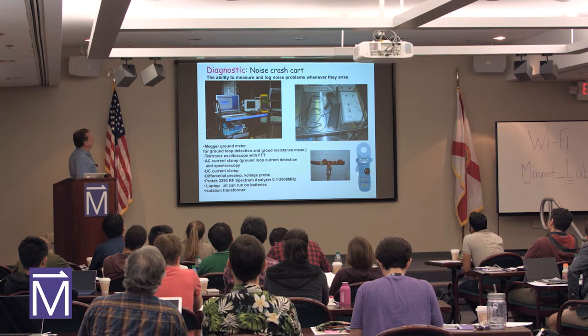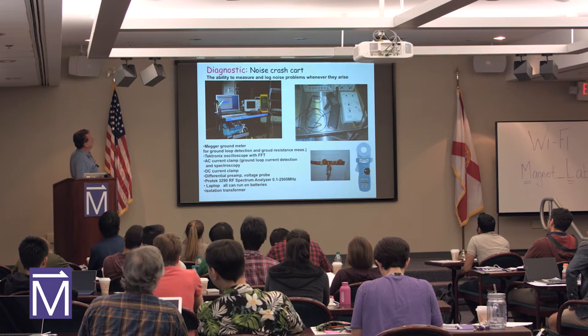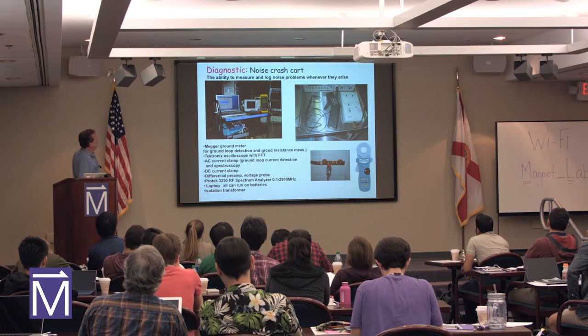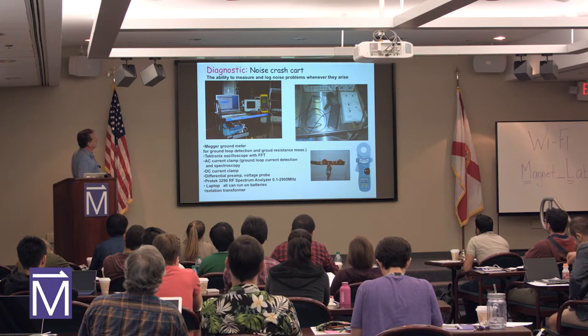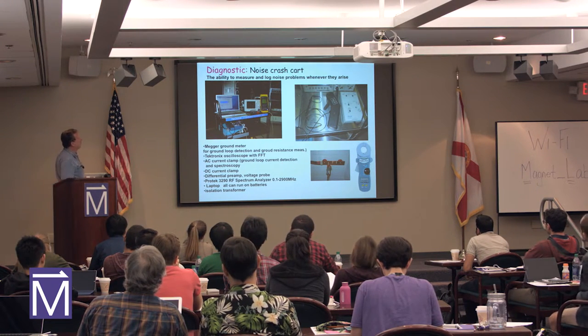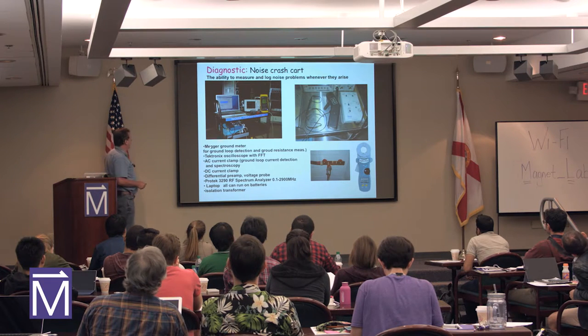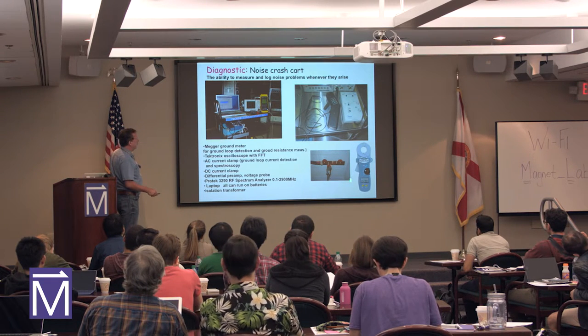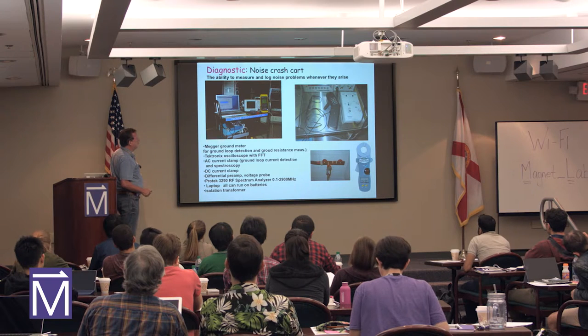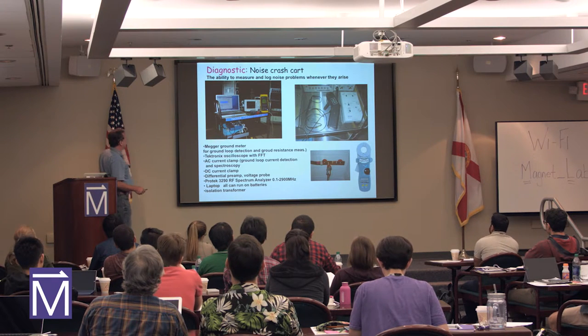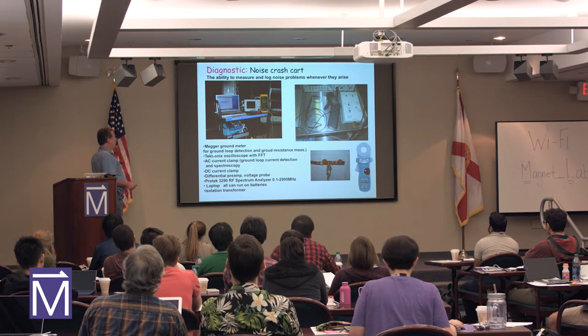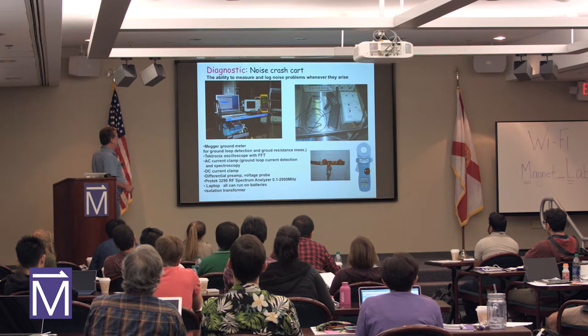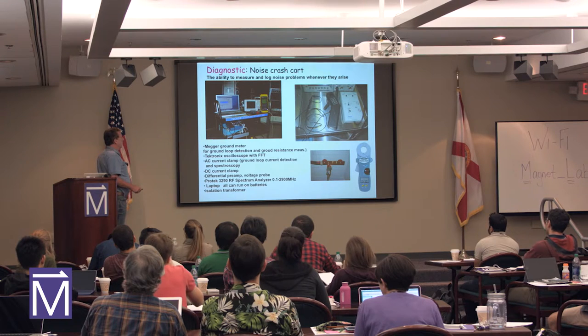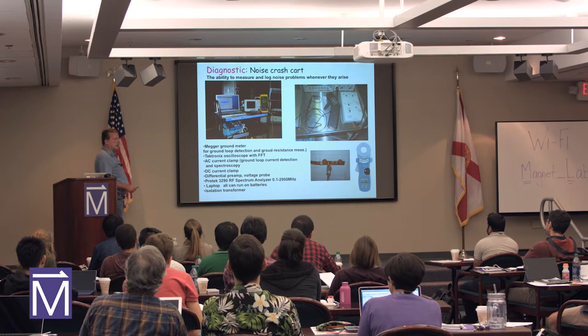Diagnostics. What we have, we put some devices on this noise crash cart, as we call it. We have two of them, and it contains a ground meter, this. Megger is a company; now we also have one from Fluke, which is the most important device here, and we can chase ground loops very quickly and also measure ground resistance.